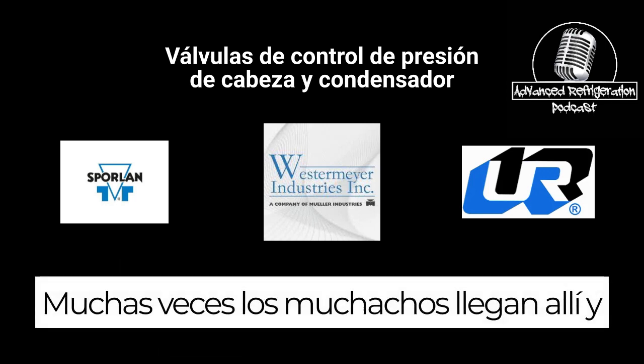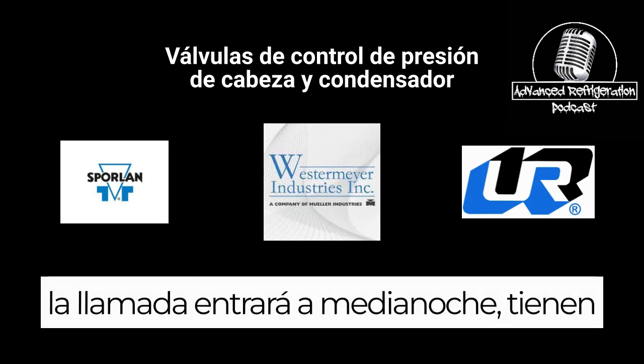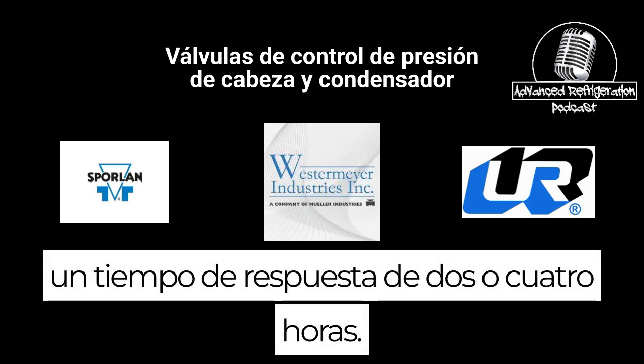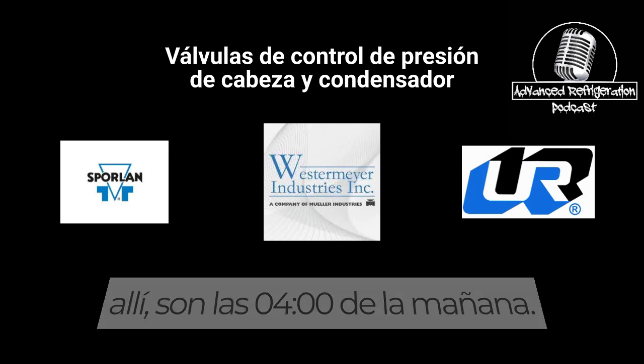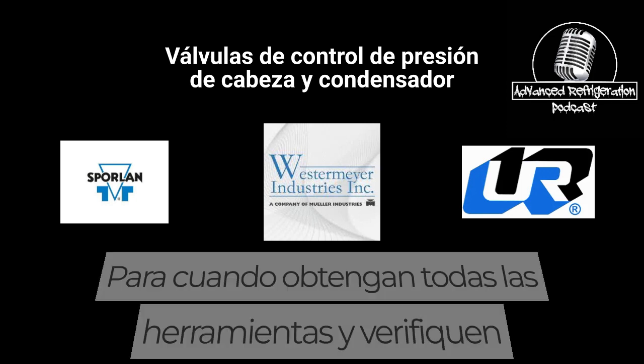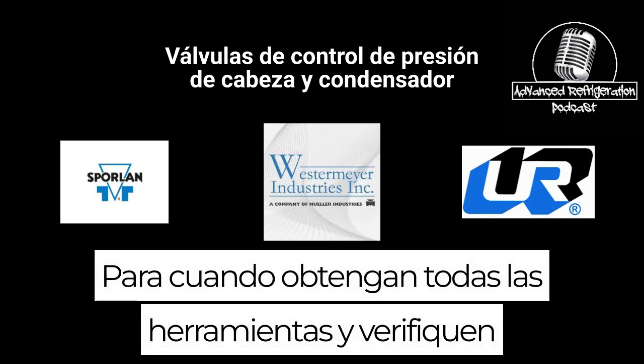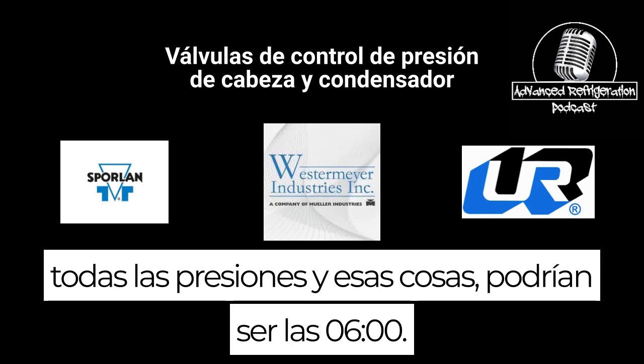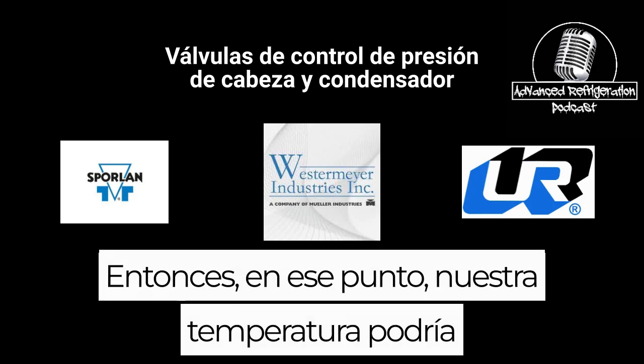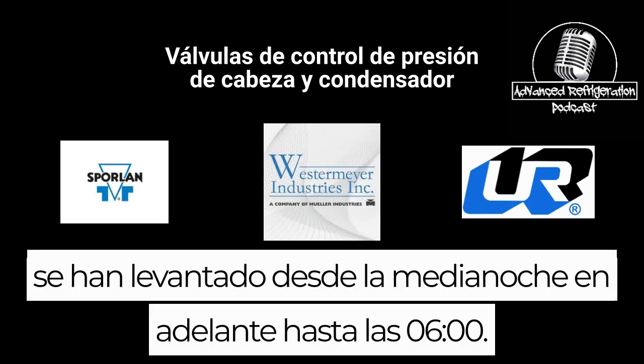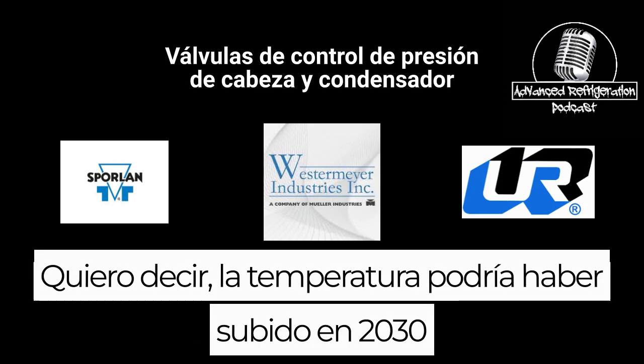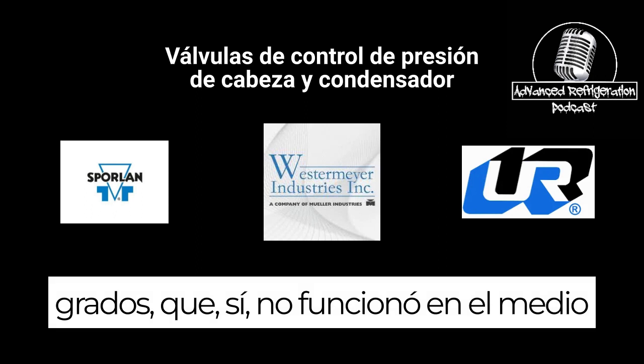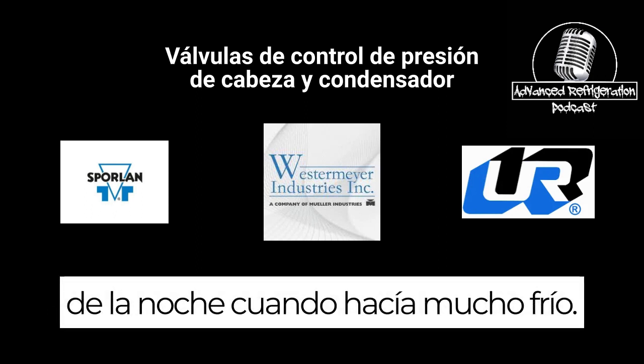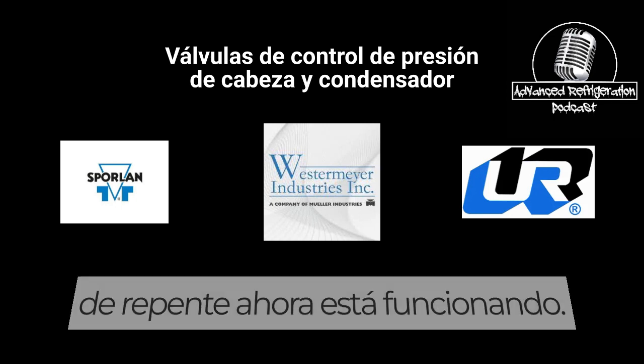A lot of times guys will get there and the call will come in by midnight. They have a 2 or 4 hour response time. So by the time they get there, it's 4 o'clock in the morning. By the time they get all the tools and check all the pressures and stuff, it might be 6 o'clock. So at that point, our temperature might've risen from midnight until 6 o'clock. I mean, the temperature might've gone up 20, 30 degrees, which yeah, it didn't work in the middle of the night when it was super cold, but then you get there and all of a sudden now it's working.